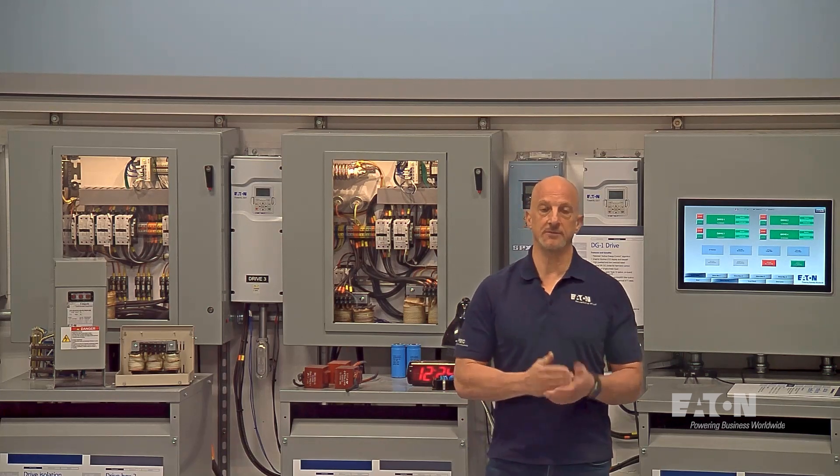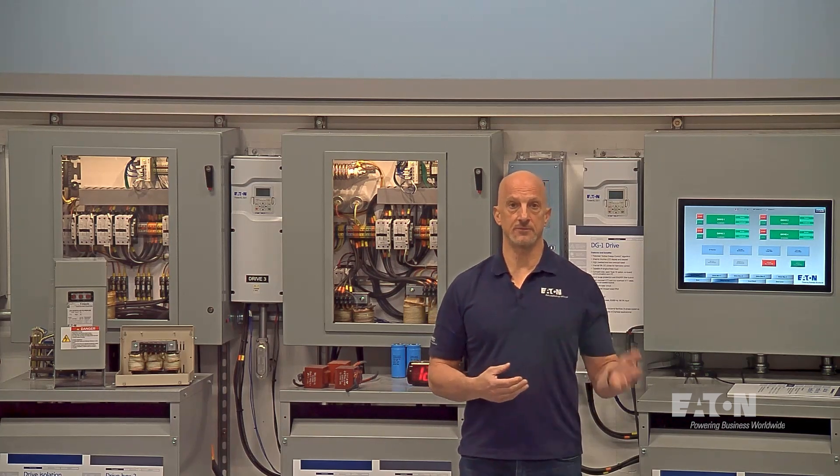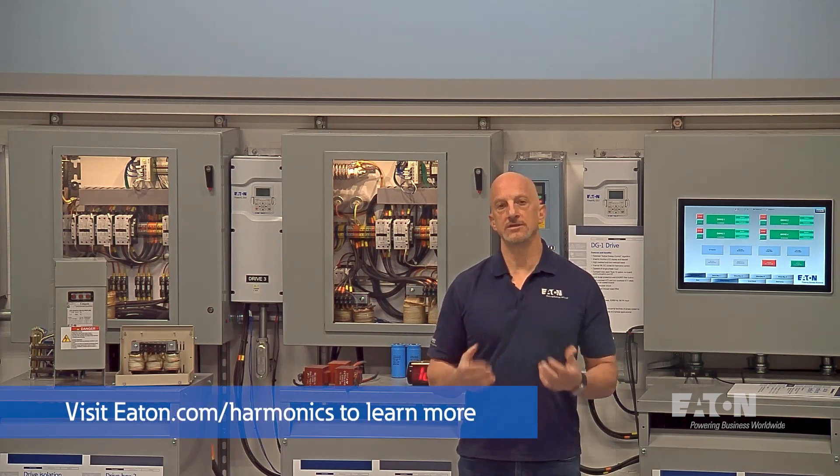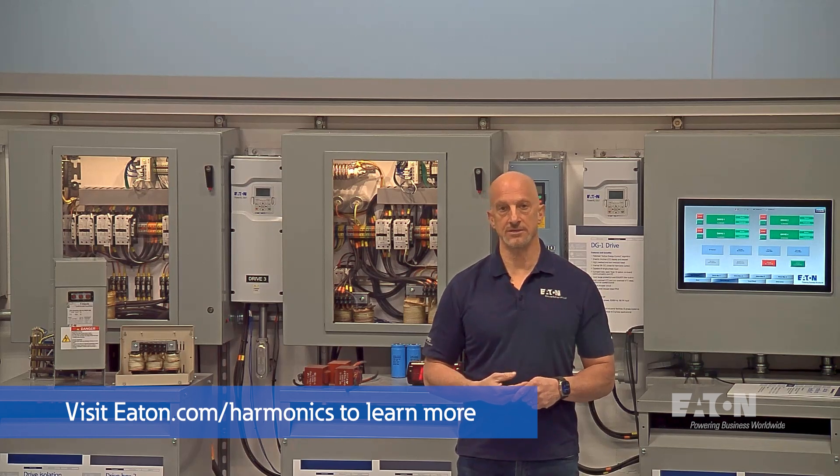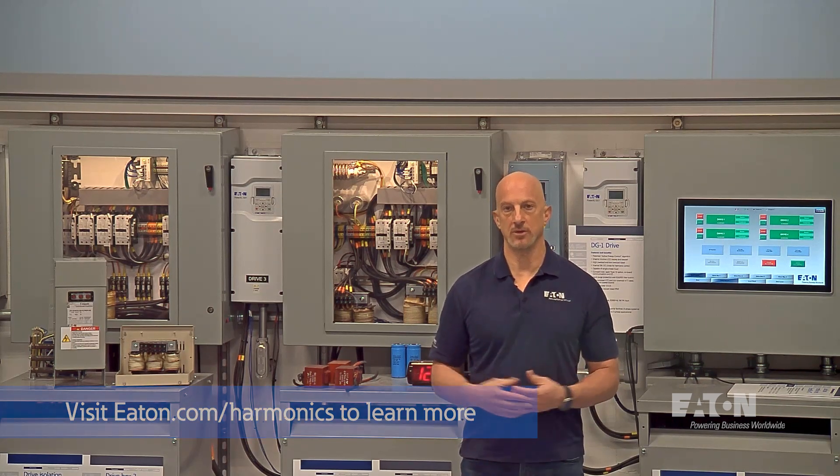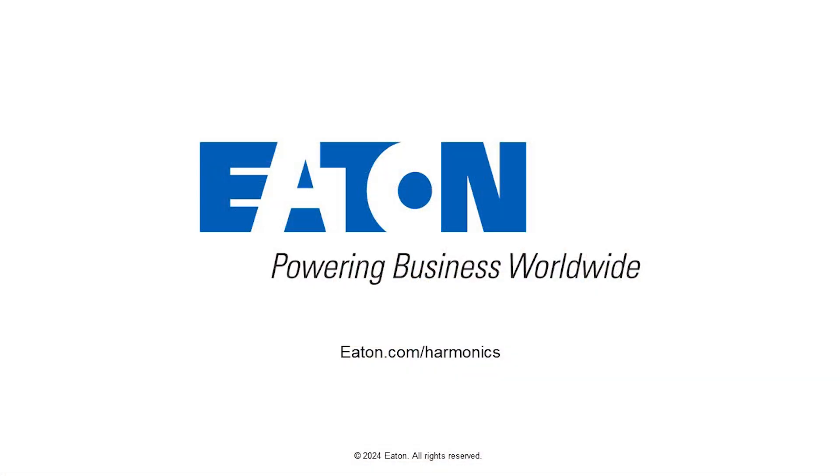And again, if I have a 12-pulse system, that NP plus or minus one is eleventh and thirteenth, twenty-third and twenty-fifth. Could be a 24-pulse system—twenty-third and twenty-fifth, and forty-seventh and forty-ninth. But anyway, those are the expected harmonics on a power system. And fortunately, they're pretty characteristically similar across the board.